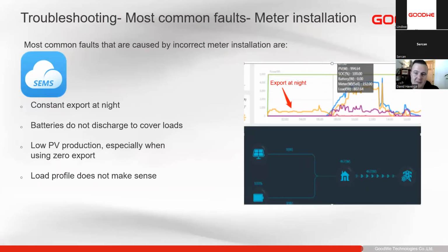So the next most common fault is the meter installation. With meter installation, we'll see that meter data is above the line, so export at night. Our batteries do not discharge and they remain full, because it is a default logic of all of our inverters. When we detect export, we will first try to use that export to charge the batteries. So if we have a third-party on-grid inverter connected, we'll try to absorb that to charge the batteries. That's why the batteries remain full.